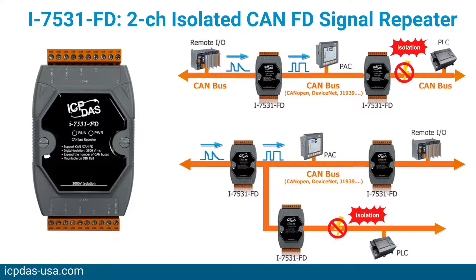The I-7531FD is a CAN-FD signal repeater which can connect two or more CAN networks with the same baud rate. Based on the signal repeat function of the module, users can use different numbers of the module to combine tree-shaped or star-shaped CAN network topology. When there are too many devices on the CAN network, using the I-7531FD can increase the driving force of the CAN signal to drive more CAN devices.